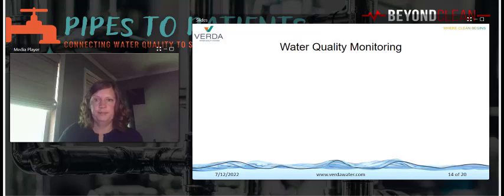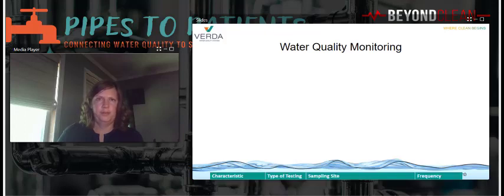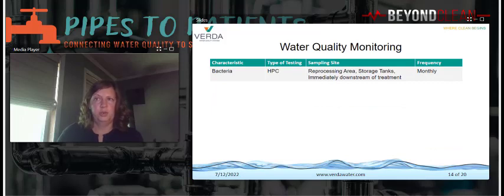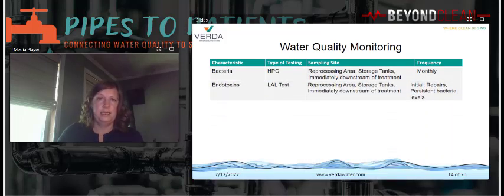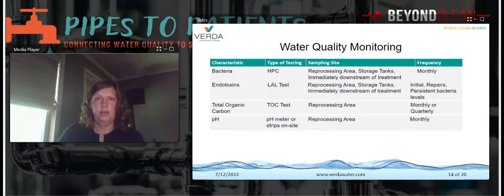So, water quality monitoring. AAMI TIR 34 recommends monitoring both water quality at the point of use as well as after each water treatment step. The rationale is to ensure water quality is maintained and doesn't deteriorate over time. If water quality isn't maintained, the water can become contaminated with inorganic and organic contaminants, including microorganisms, and contribute to corrosion, staining, and increased microbial levels after reprocessing.